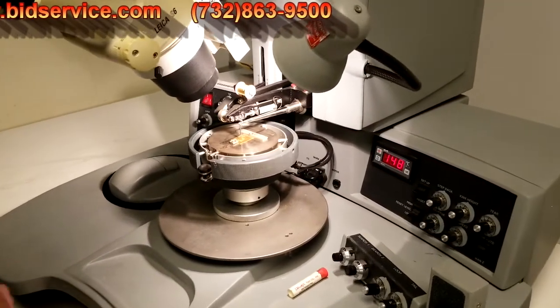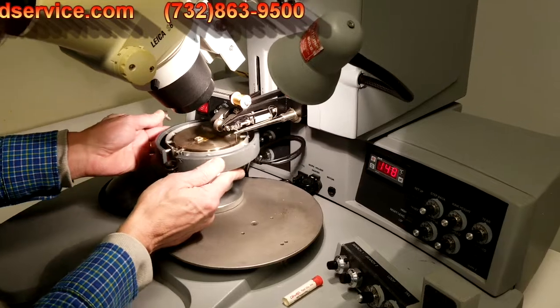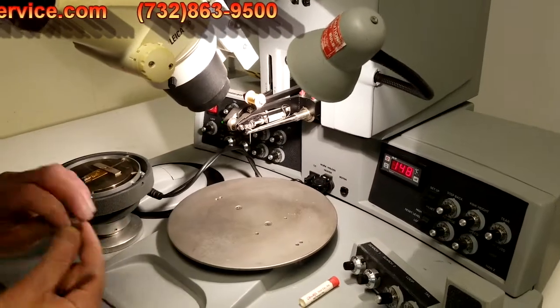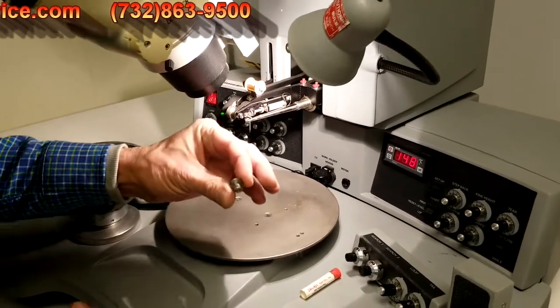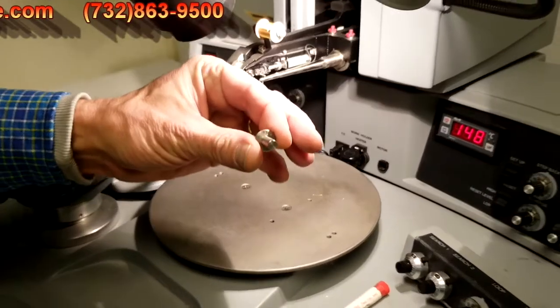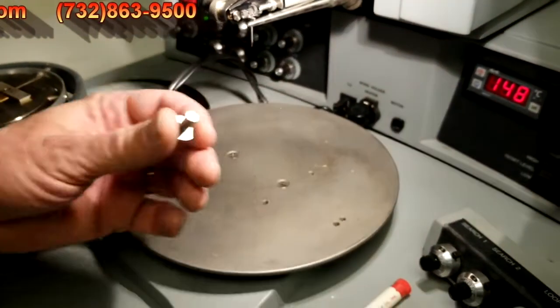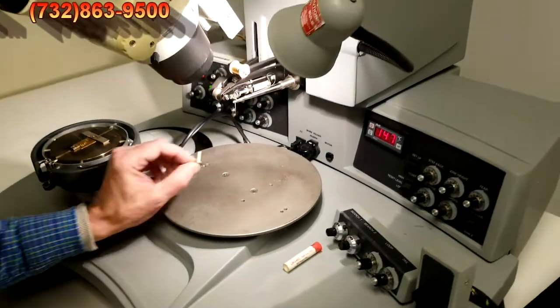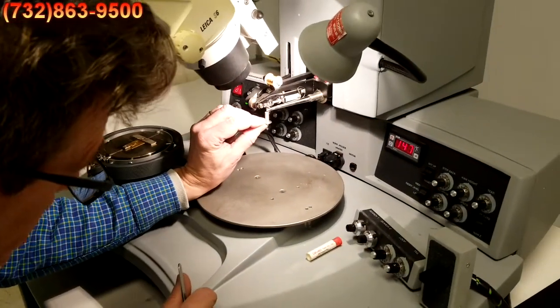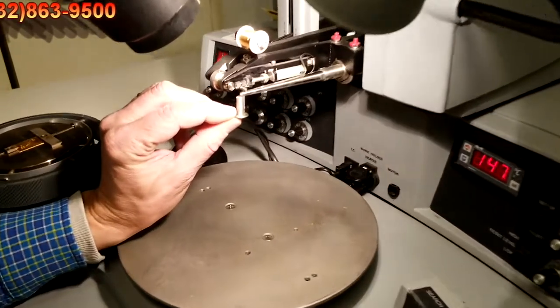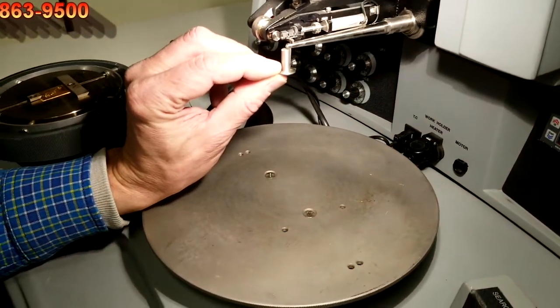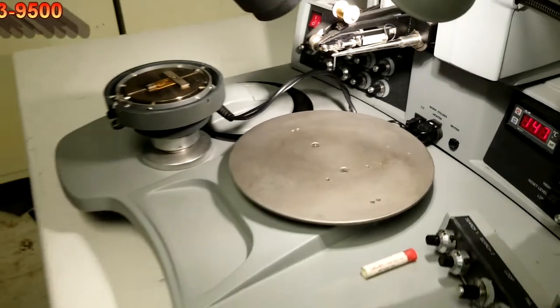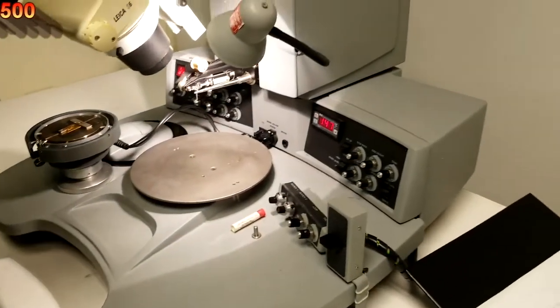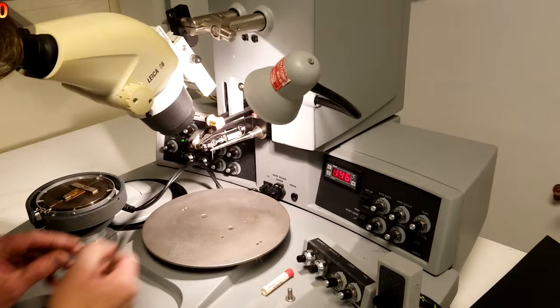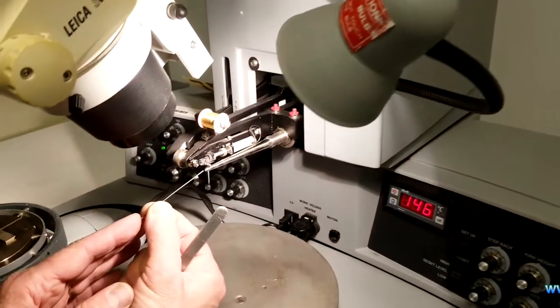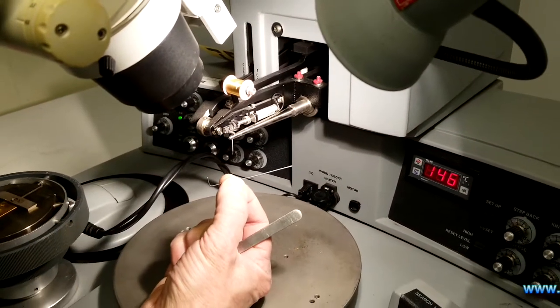If you do change the tool out, you'll need a setup tool. For the Deep Access, they require the .828. I don't know if you can see that on it. It's a .828 setup tool, and basically you just place it in there like this, and you drop your tool in. That's how you set the depth of the tool in the transducer. The set screw, in order to change it out, uses a 256 Allen wrench.